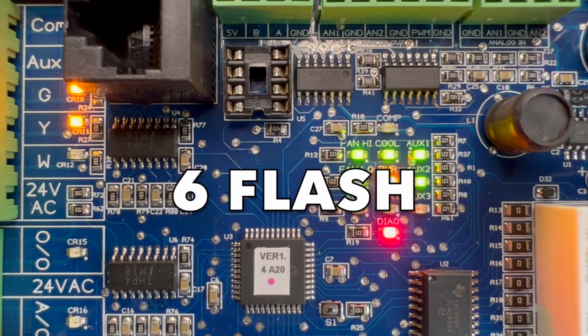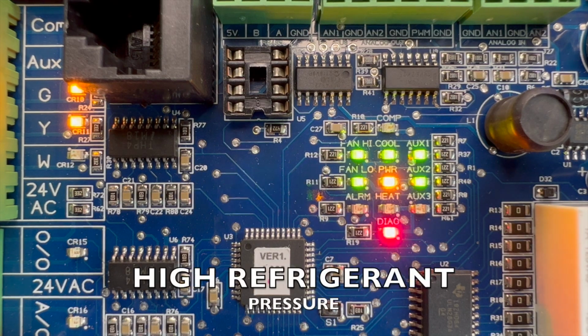Flash Code 6, High Refrigerant Pressure. This terminates compressor operation when the high pressure switch opens above 600 psi. It will reset when the pressure drops below 450 psi. This prevents compressor startup if the switch is open, and full lockout will occur if there are 3 trip outs in a 24-hour period, which are 10 minutes or longer.